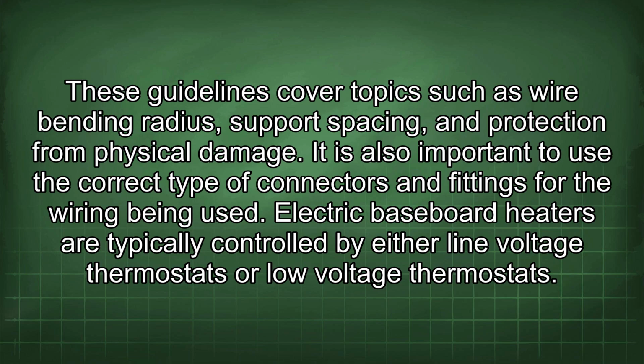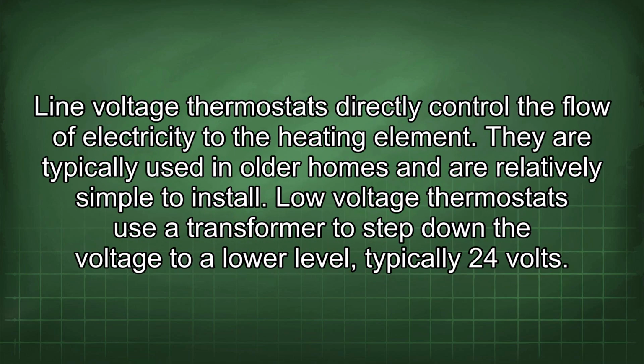It is also important to use the correct type of connectors and fittings for the wiring being used. Electric baseboard heaters are typically controlled by either line voltage thermostats or low voltage thermostats. Line voltage thermostats directly control the flow of electricity to the heating element. They are typically used in older homes and are relatively simple to install.